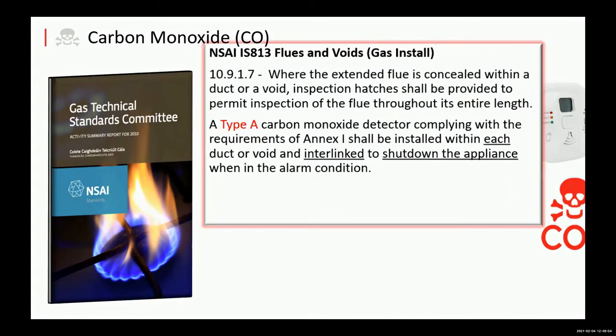Where it does come into play is if you extend onto that flue. Where the extended flue is concealed within a duct or a void, inspection hatches shall be provided to permit inspection of the flue throughout its entire length. And a Type A carbon monoxide alarm complying with the requirements of Annex I shall be installed within each duct or void and interlinked to shut down the appliance. It's the only time you'll see interconnection of carbon monoxide alarms in the standards. There's no requirement in Part J. There is in IS 813, and that is interconnected to shut down the appliance. So it has to be connected to a relay device or other types of devices to shut down the appliance.